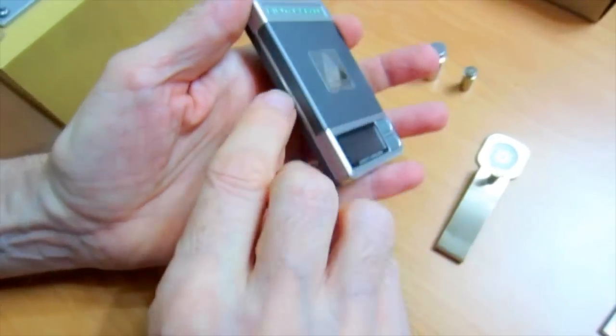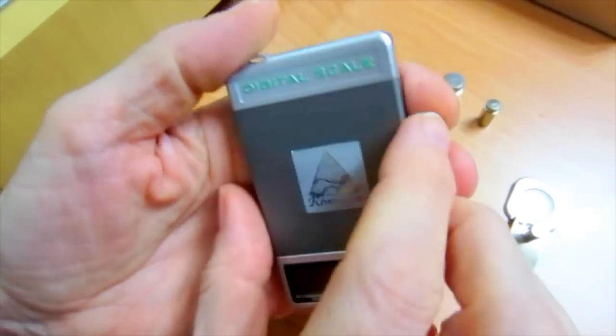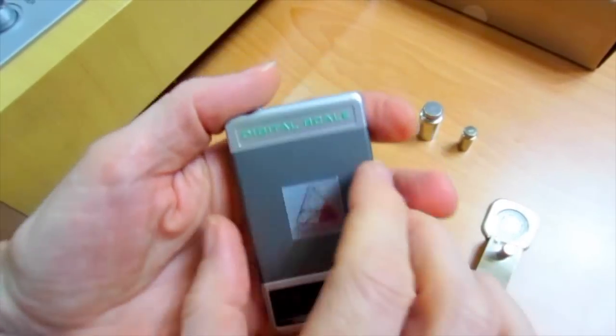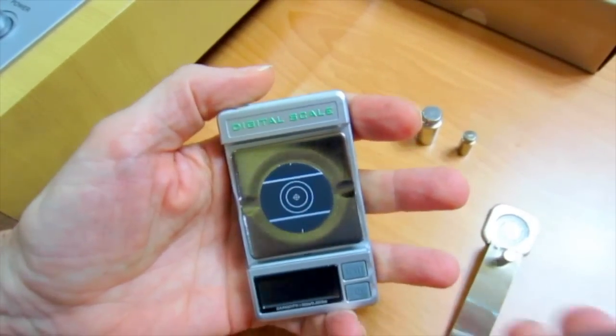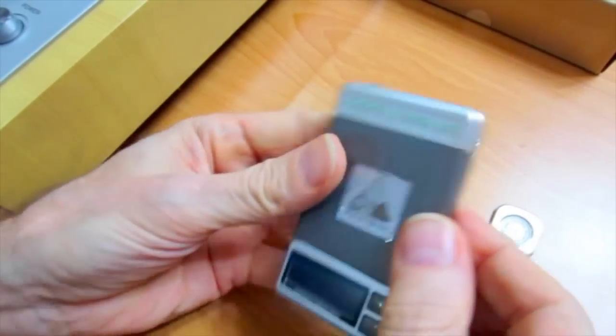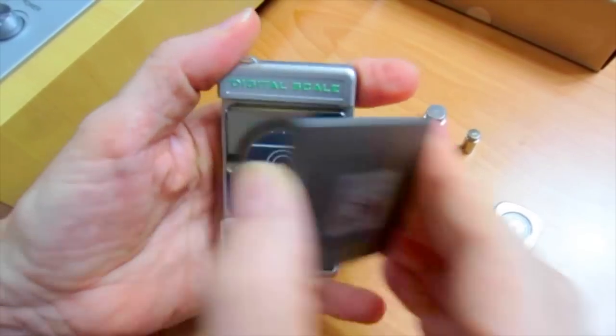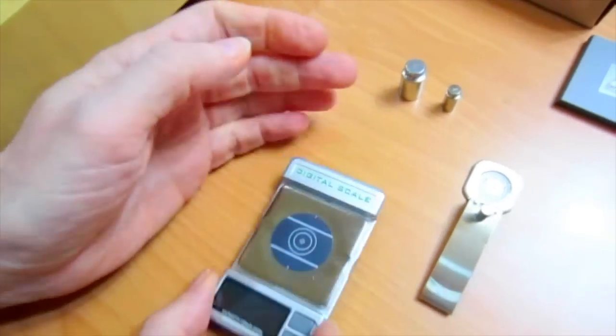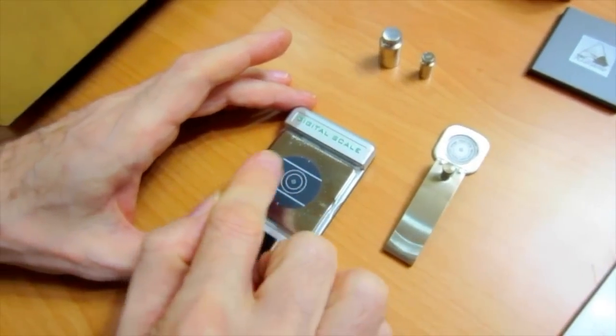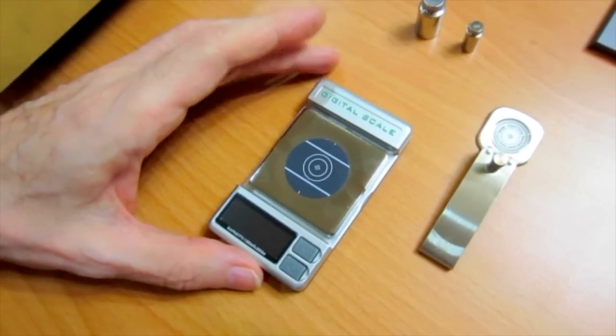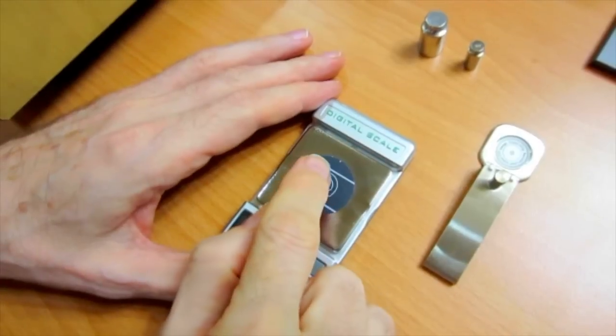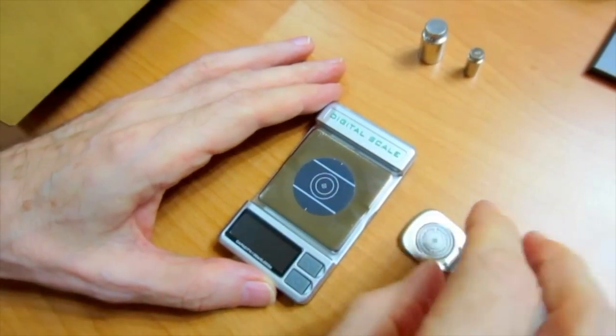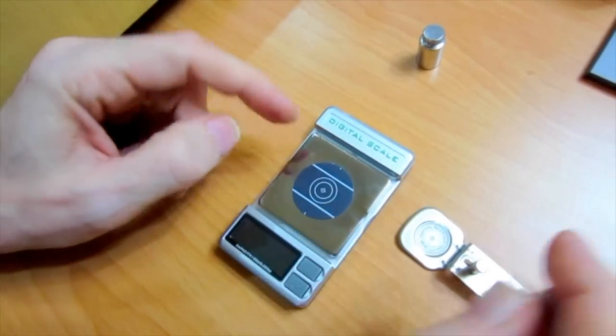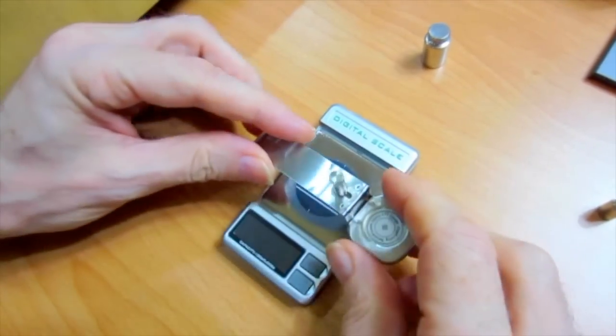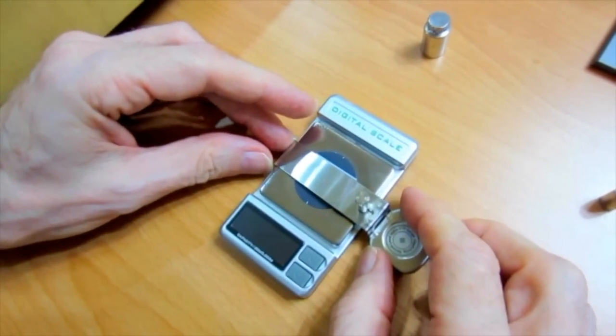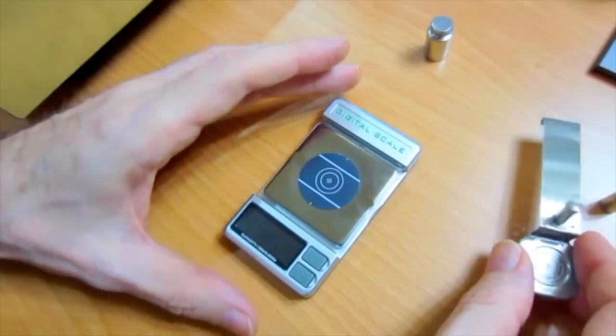To take the cover off, you'll notice two indentations here. Hold the gauge top and bottom and just gently pull it off, and you can snap it back in to protect the strain sensor when you're done. Alright. Now this is the central loading platform. Beneath here is a precision strain gauge sensor, the strain gauge beam. This is a polymer pad, and you'll notice some lines on here, horizontal lines. Those essentially are guidelines when we place the extension arm on. I'll show that in a moment.